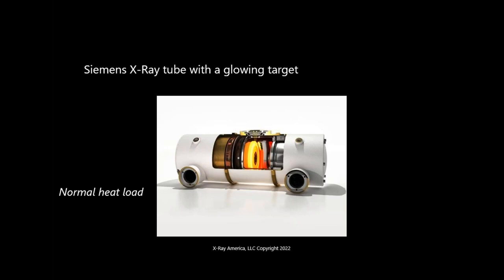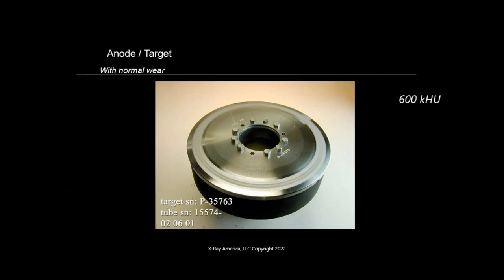CT is even much worse because you've got the combination of not just the rotating anode, but you've also got the entire tube rotating targets. So this is the anode. This is our target, the target assembly. This one is probably a 600 KHU because of the graphite back. This is the track. So this spins. This is where the electron beam hits. Because it's spinning, it makes an effective target area which is many, many times bigger than if it was stationary. And as it spins, of course, it cools and radiates heat. So that's a normal one. And here I have a normal anode. That's about a 400 KHU too.